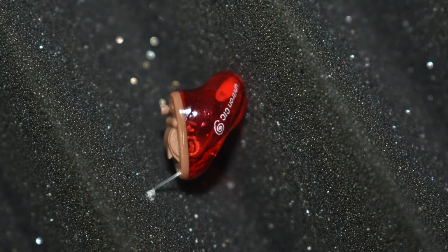All hearing aids that sit inside the ear canal are custom molded to the ear. An ear impression is taken by your audiologist, which is then sent into the hearing aid manufacturer. All of the hearing aid components are then fit inside the custom casing. The smallest hearing aid in my collection is a CIC. CIC stands for Completely In Canal. This one is red to show me that it's made for the right ear. If it was for the left ear, it would have a blue casing. It uses a small battery size 10.